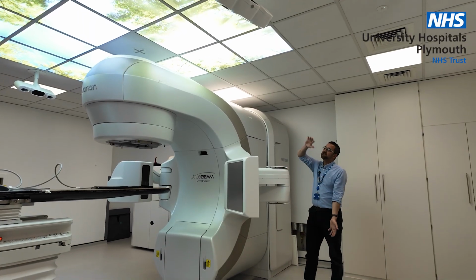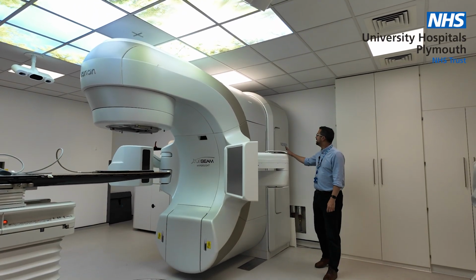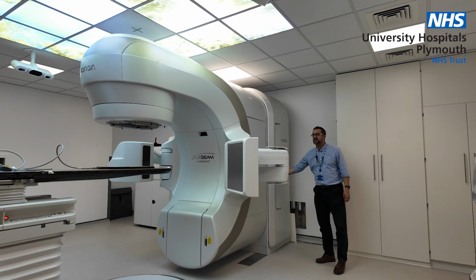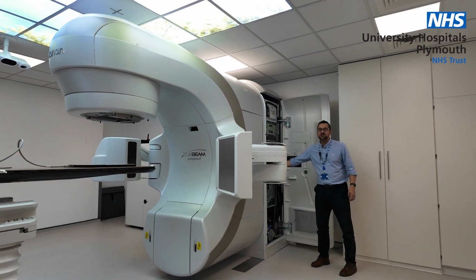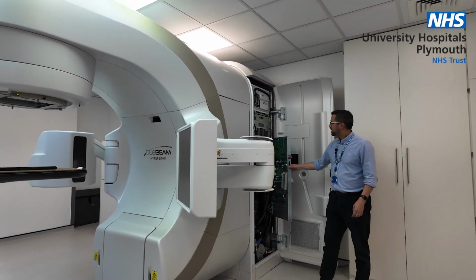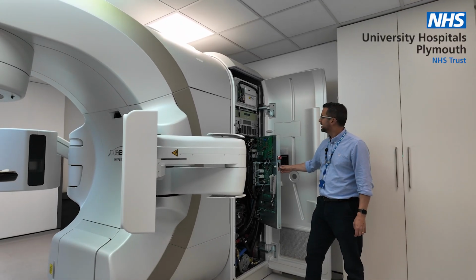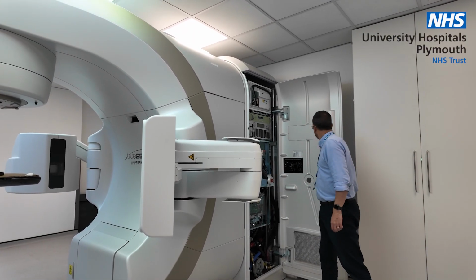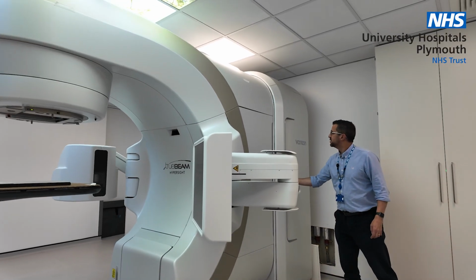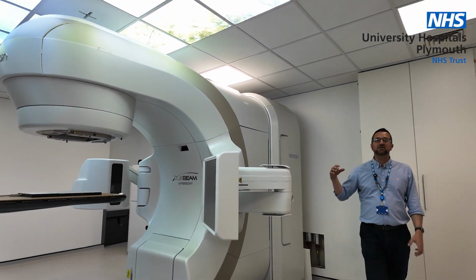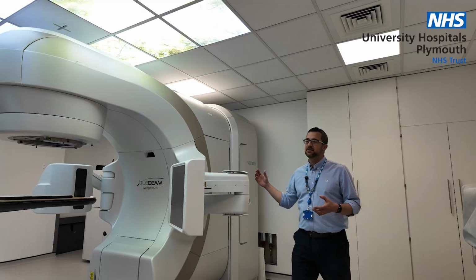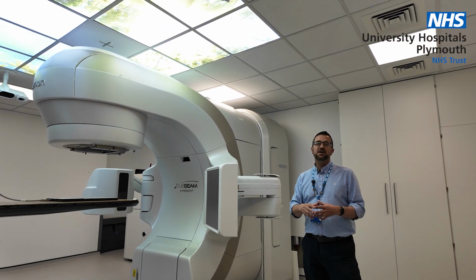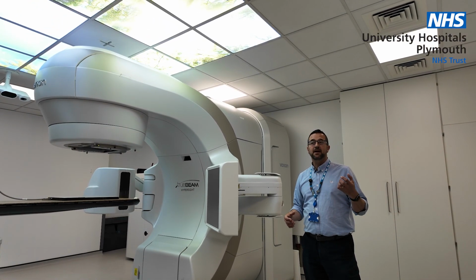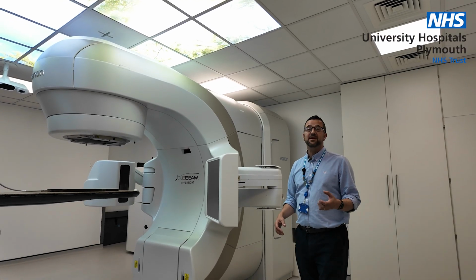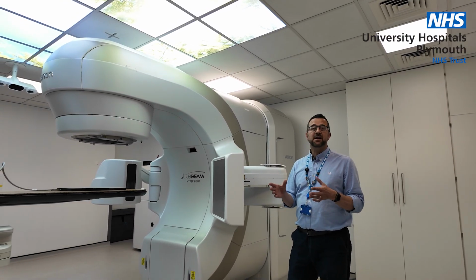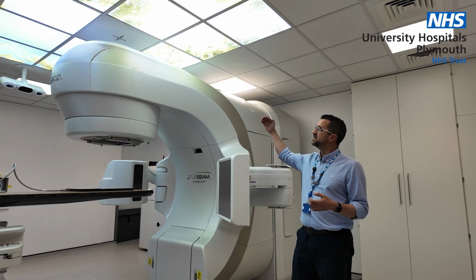This big part that rotates around is called the gantry. The rear part here is called the stand. The stand contains all the control electronics, the brains of the machine. So we generate a very high DC pulse, which we then send to something called a klystron, which generates RF microwave power, typically around 20 megawatts. We inject that into the accelerator guide.